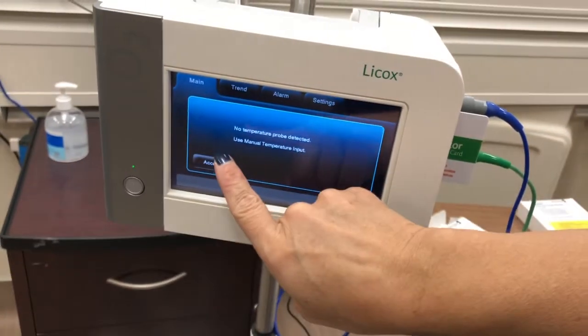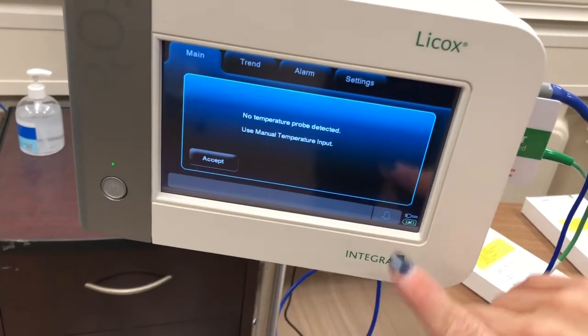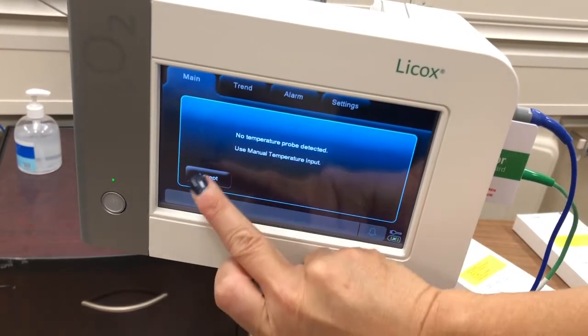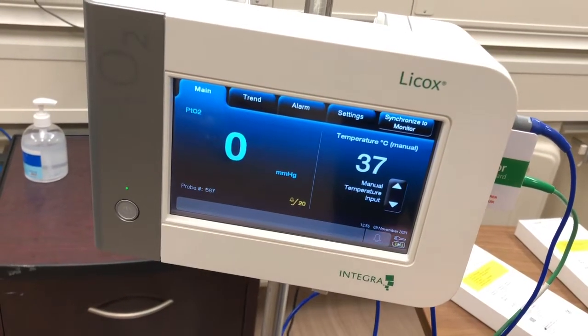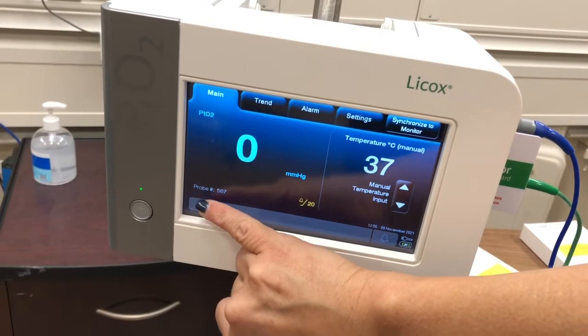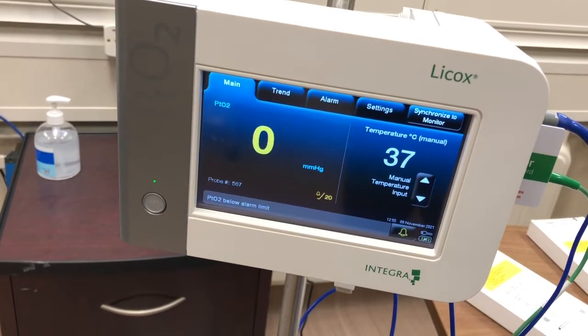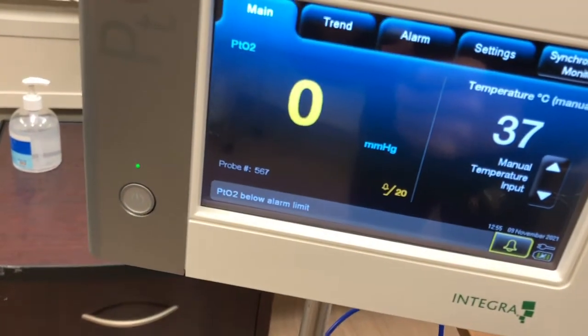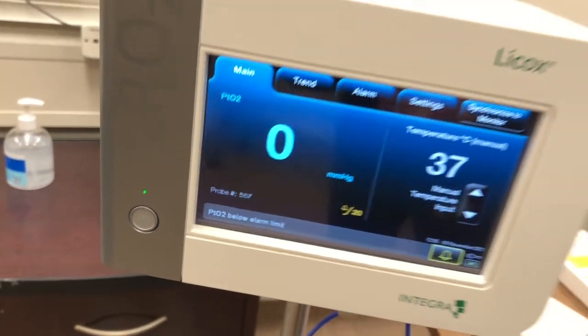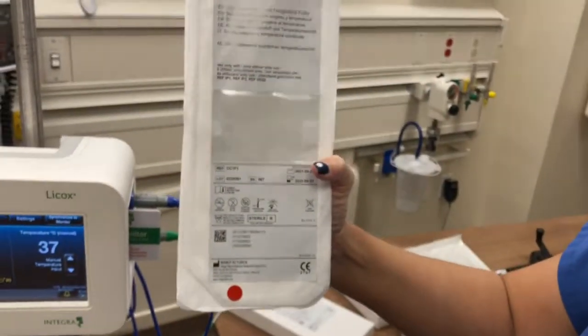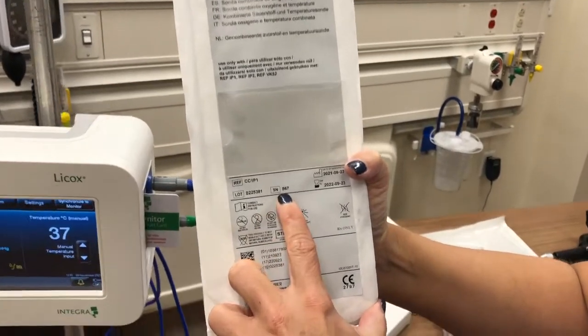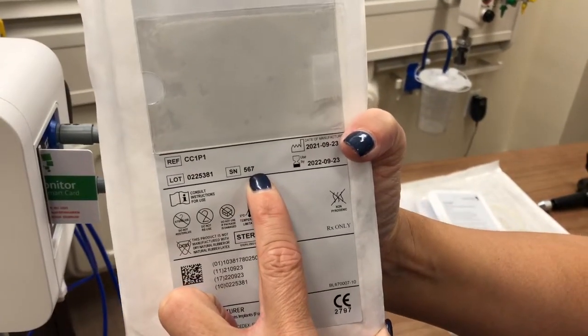It clicks in, you'll feel it seat. It has the little chip on it like your credit card. And then it's going to say no temperature probe detected, use the manual temperature input. But you're going to accept that because it just illuminated probe 567. And that's what's on that card. And of note, this is that particular probe. It says 567 serial number.